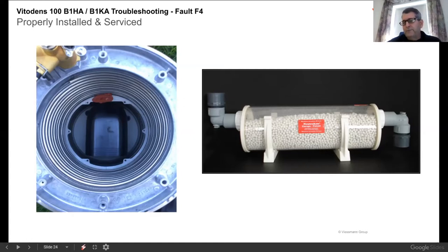What I always explained to people was, when I first started putting these boilers in, when they first came out, nobody was talking about neutralization. The supply houses didn't know about it. So we were making them out of PVC, and we were putting the pellets in there, and we weren't sure if they were the right size. But now in the manuals, they all give you how much condensate these boilers produce within an hour. I have two 22s on one condensate pump, because as much condensate as I could produce, that one pump that I put in with the neutralizer could handle both boilers.